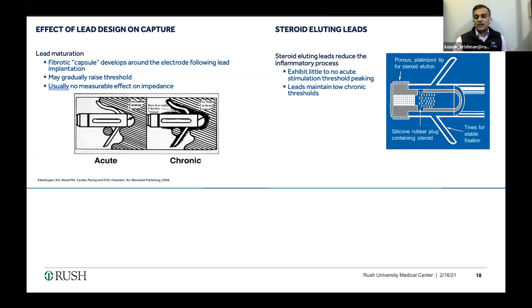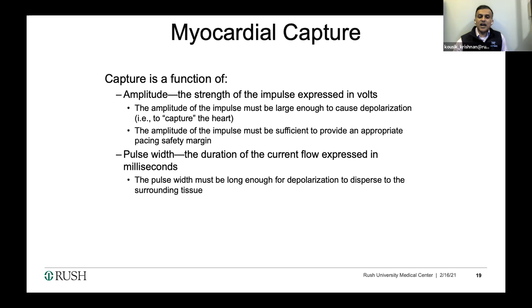So myocardial capture is a function of the amplitude of the voltage output of the battery and the device, which needs to be large enough to cause depolarization or capture. And we also have a pulse width. The output of the device is an amplitude and a duration of that voltage being supplied for a certain amount of time, and that is called the pulse width.